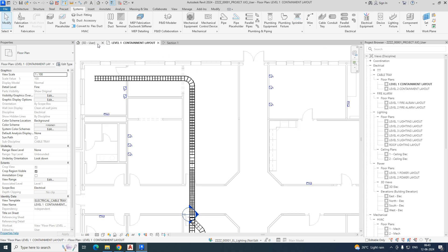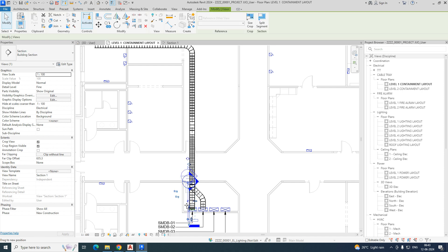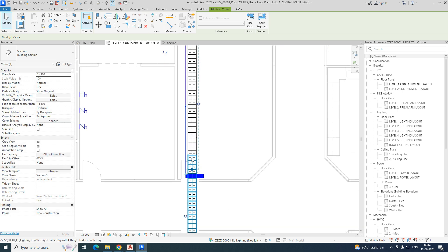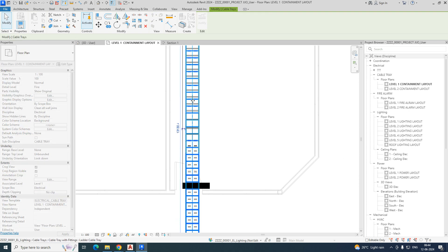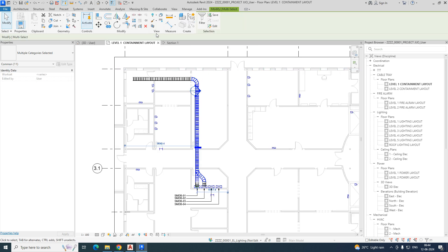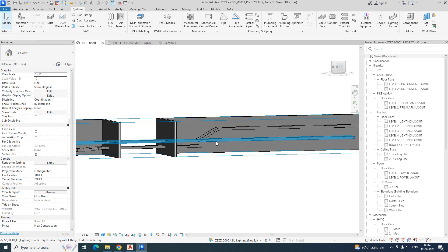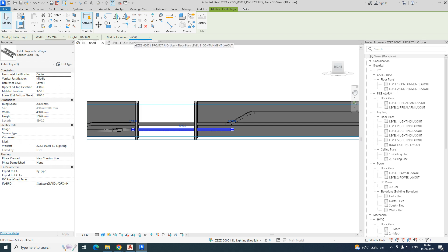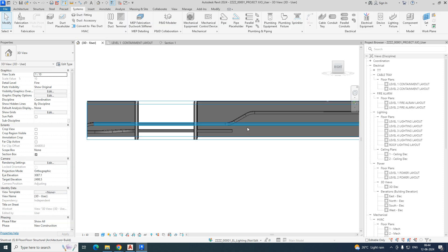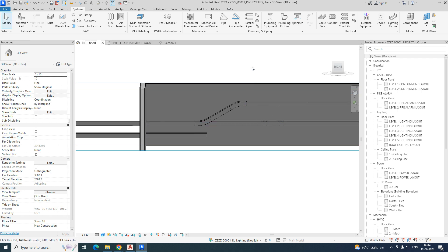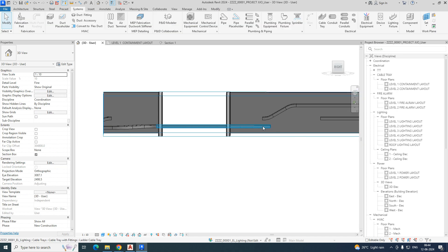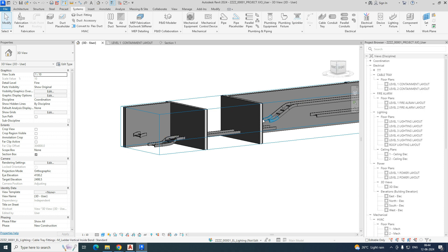To connect the trays, it is better to make a section so you can select and connect them more easily. Sometimes what happens is it does not connect properly — this cable tray was not connected at this point. So I'm changing the elevation. I split it again — SL is the split command — delete this part, and the two cable trays are connected together.